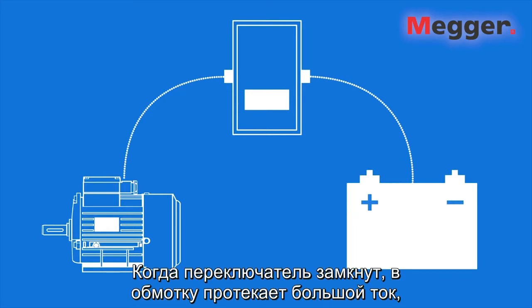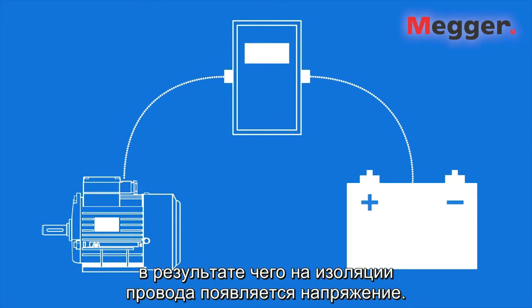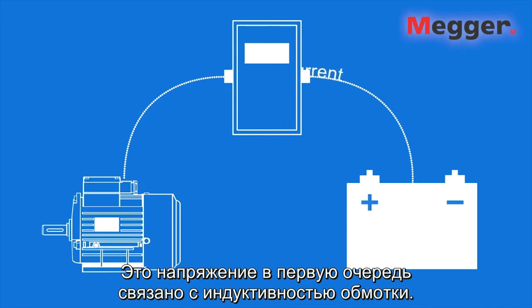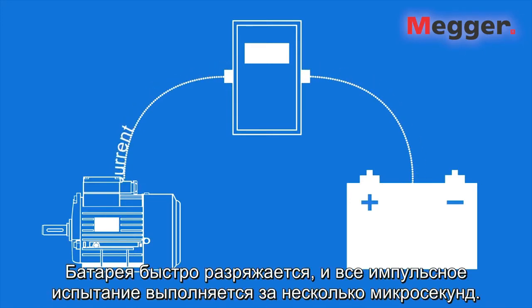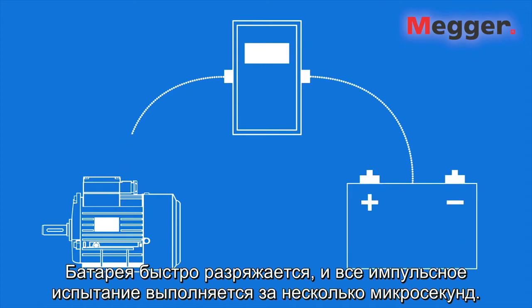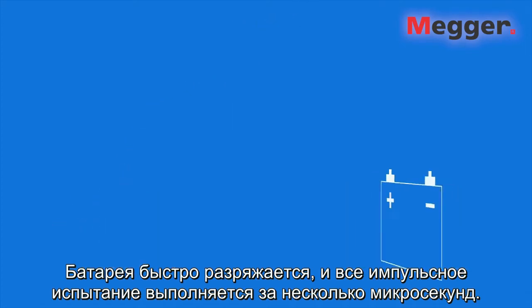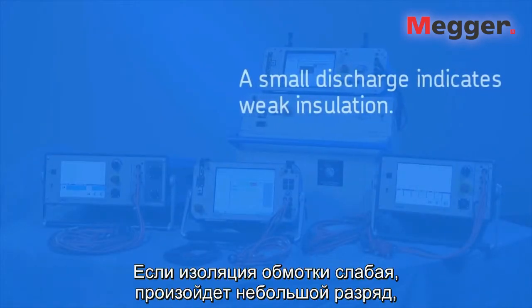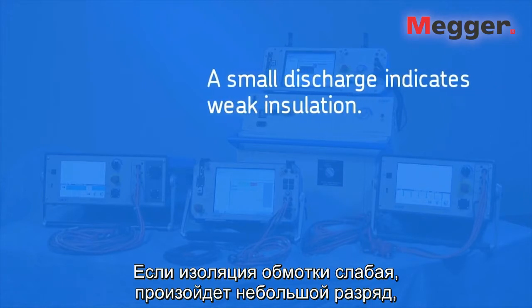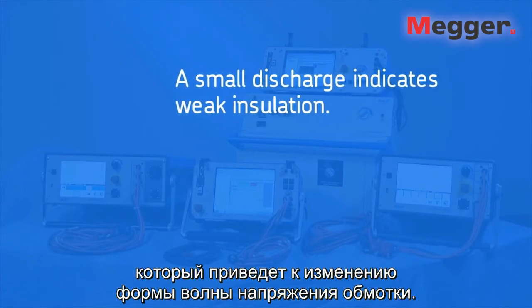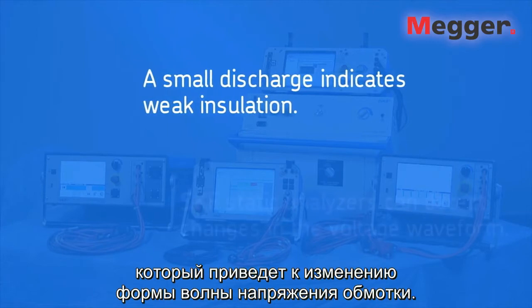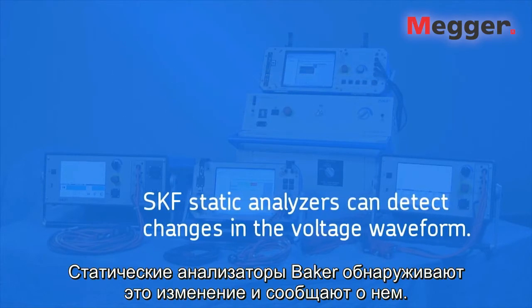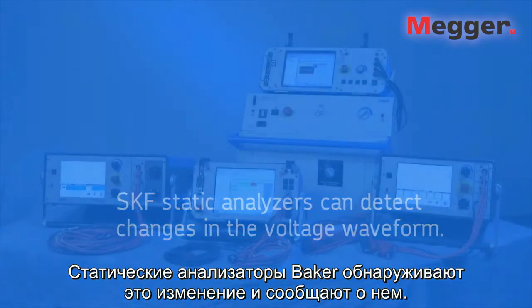When the switch is closed, a large amount of current flows into the winding, causing a voltage to appear across the wire insulation. This voltage is due primarily to the inductance of the winding. The battery quickly discharges and the whole surge test is done in a few microseconds. If the winding insulation is weak, a small discharge will occur, which causes the voltage waveform of the winding to change. Static analyzers detect and report this change.